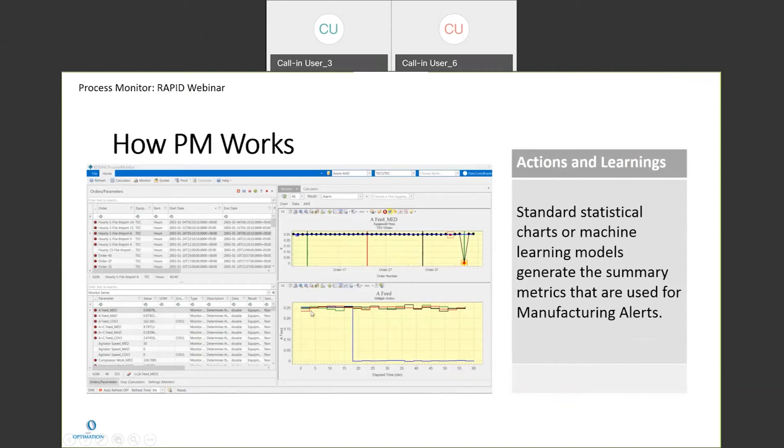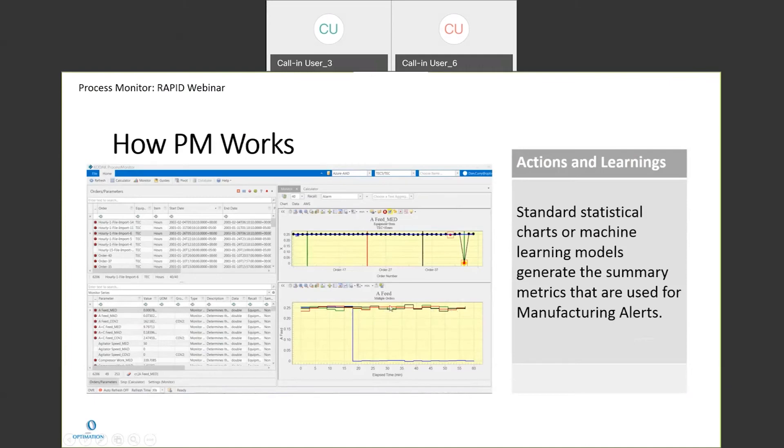And it's pretty obvious here on this blue batch, something is quite different than normal. These other three - there's a red, a green, and black - and they're all hovering right around 0.25 kilograms per minute or whatever the flow rate values are. But in this case, this one dropped down to zero.